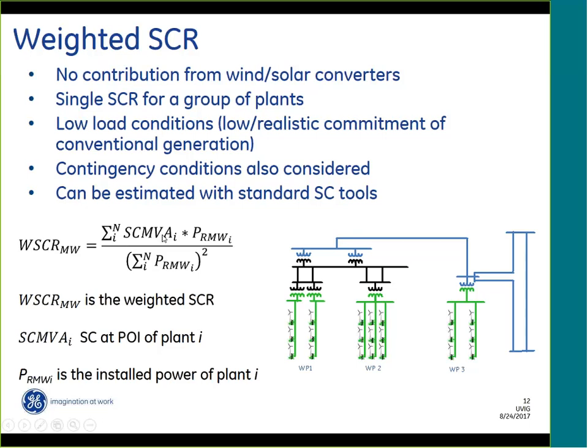So in this particular example, I will have 3 wind plants. So I will have short circuit MVA of bus number 1, which would probably be the short circuit level at this bus. And then I will have the short circuit level of the second plant at this bus. And then for the third plant it could be at this bus over here.